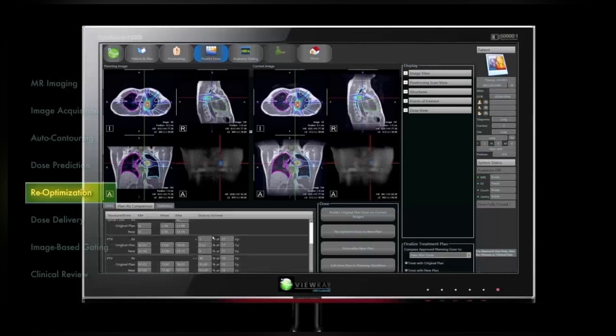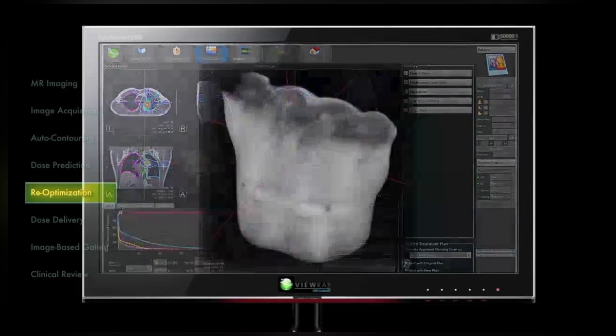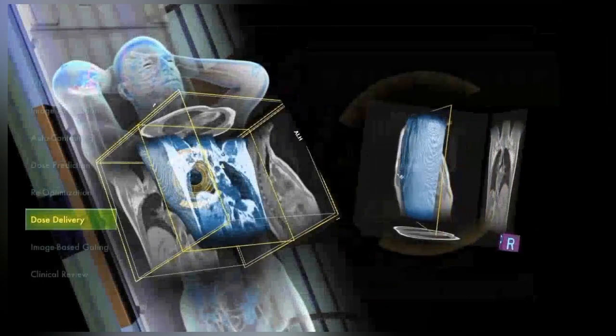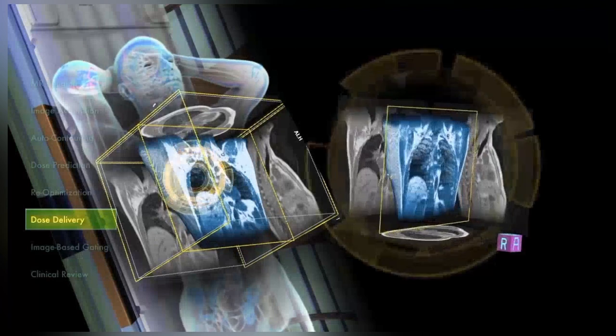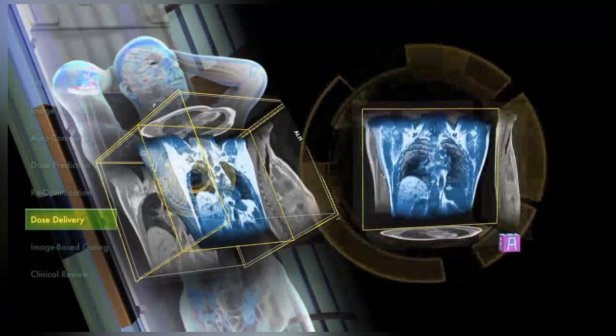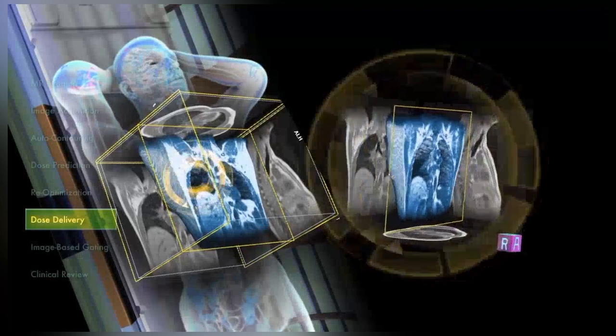With the ViewRay system, the dose prediction and re-optimization is performed in under 2 minutes. Once treatment begins, the MRI captures a continuous stream of soft tissue images — every 250 milliseconds in a single plane and every 500 milliseconds for 3 planes.